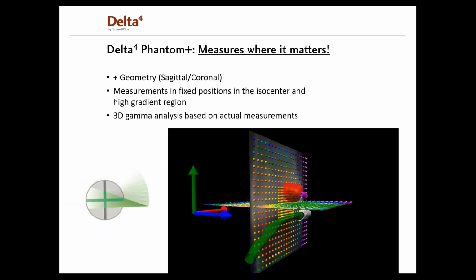The geometry of the detectors in the Delta4 Phantom Plus has a plus configuration, hence the name Phantom Plus. This is a patented configuration based on two orthogonal detector planes aligned in the cardinal directions in a fixed geometry, providing full coverage of the cross-section of any beam direction. Thereby, the intensity modulation of the treatment delivery can be verified without missing any data. This also means that we now measure in the sagittal and coronal planes, and this is often preferred as it corresponds to the planes that are used when the patient is planned in the TPS.